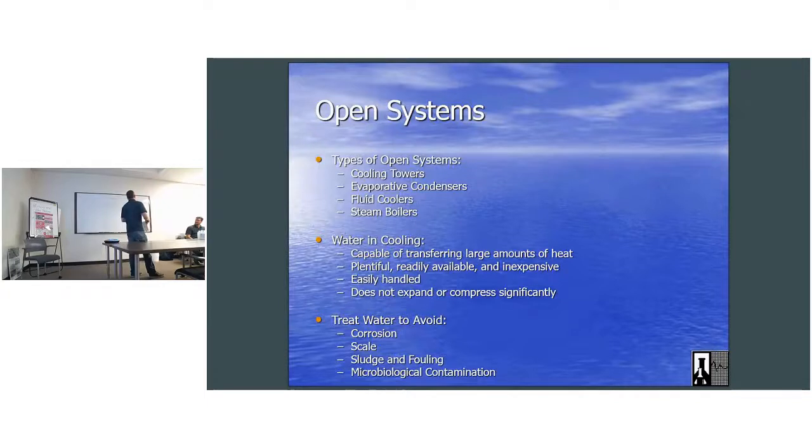Anything over roughly 600 parts per million is when your water starts getting thick and you start getting scale on the pipe. That's why the industry standard is a little lower, at 440. So if you run into a problem and your bleed's not working for a little bit, you have a little wiggle room, and you're not immediately building scale.